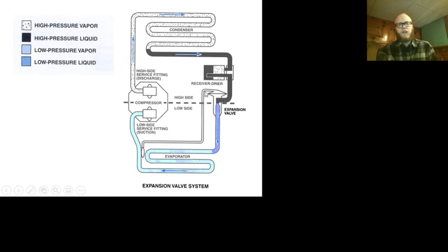And the way that it can tell what it needs to do is this little sensing bulb that is touching the outlet of the evaporator. So it's able to tell what the temperature is of the refrigerant leaving the evaporator. And so that way it can tell, well, if this is too warm, I need to add more refrigerant to the evaporator, cool things down a little bit more. If this is too cold, well, we run the risk of sending liquid refrigerant into our compressor at that point.